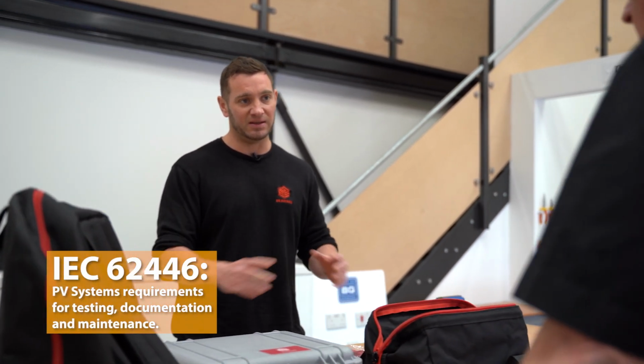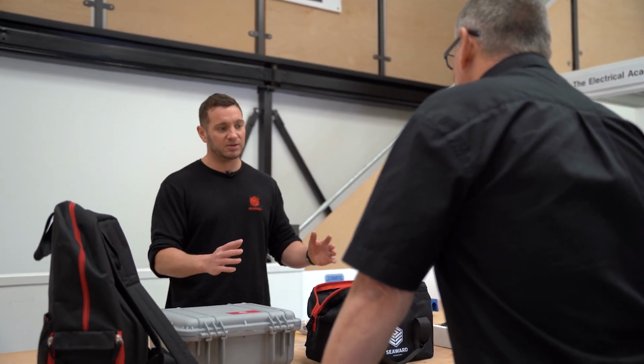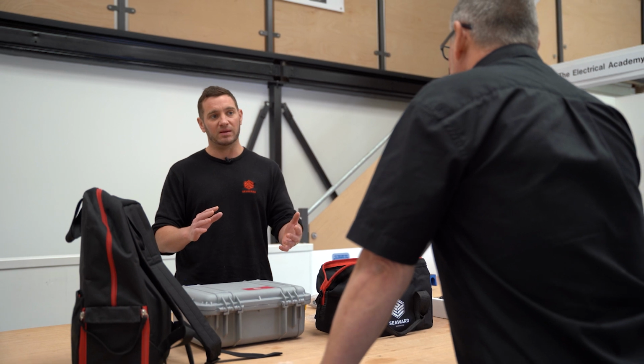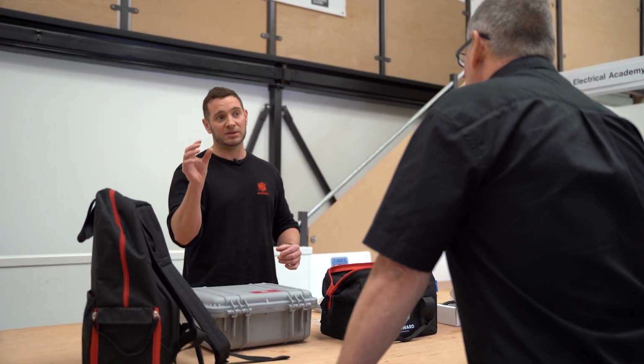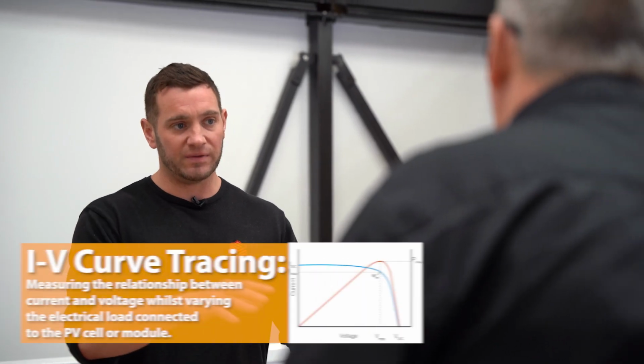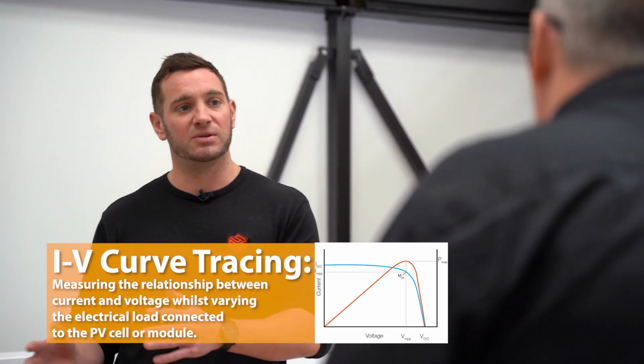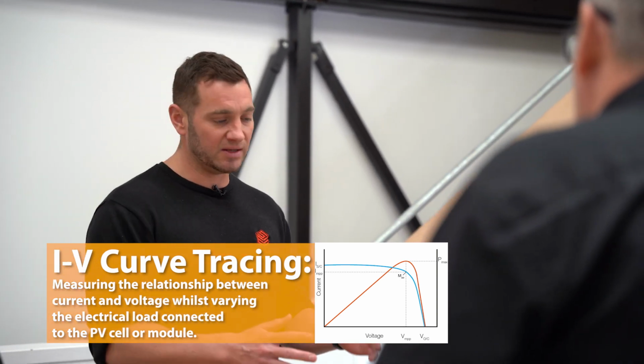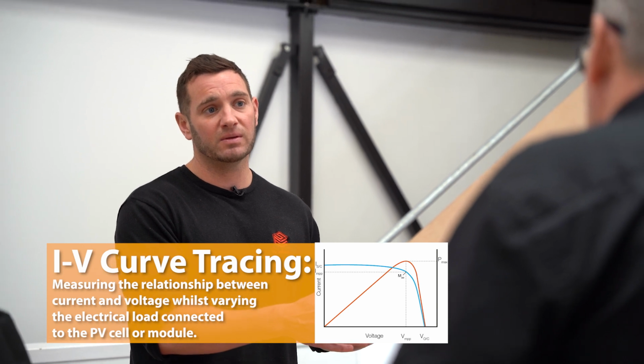The main standard in solar is IEC 62446. That's the standard they expect everybody to comply to. So what we had to do is create a tester that complied with the specific testing element for 62446, where IV curve tracing didn't exist back in 2011-2012. We had something called the PV150, which was sufficient for that time.